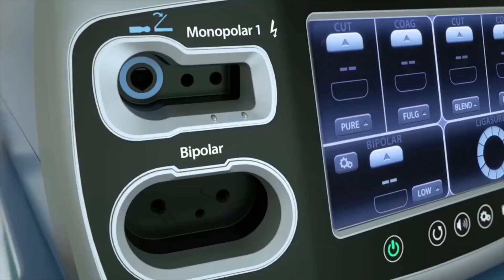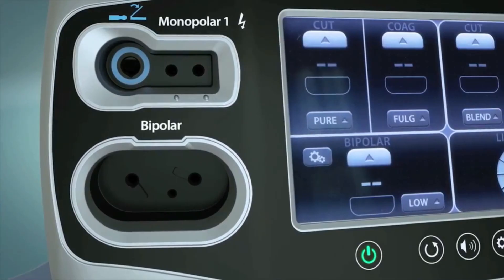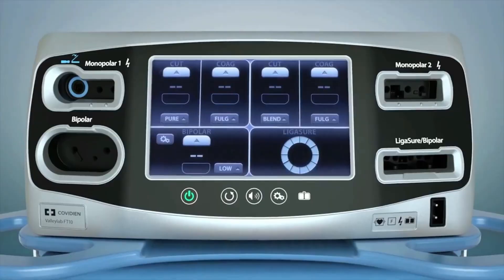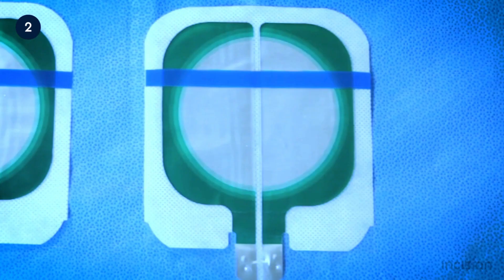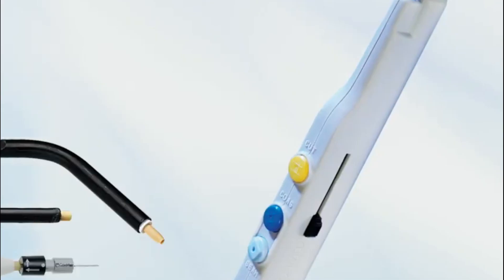Let's look into the components of an electrosurgical unit. An electrosurgical unit, or ESU, consists of a generator, a handpiece, and grounding electrodes. The device is controlled using a switch on the handpiece or a foot switch.